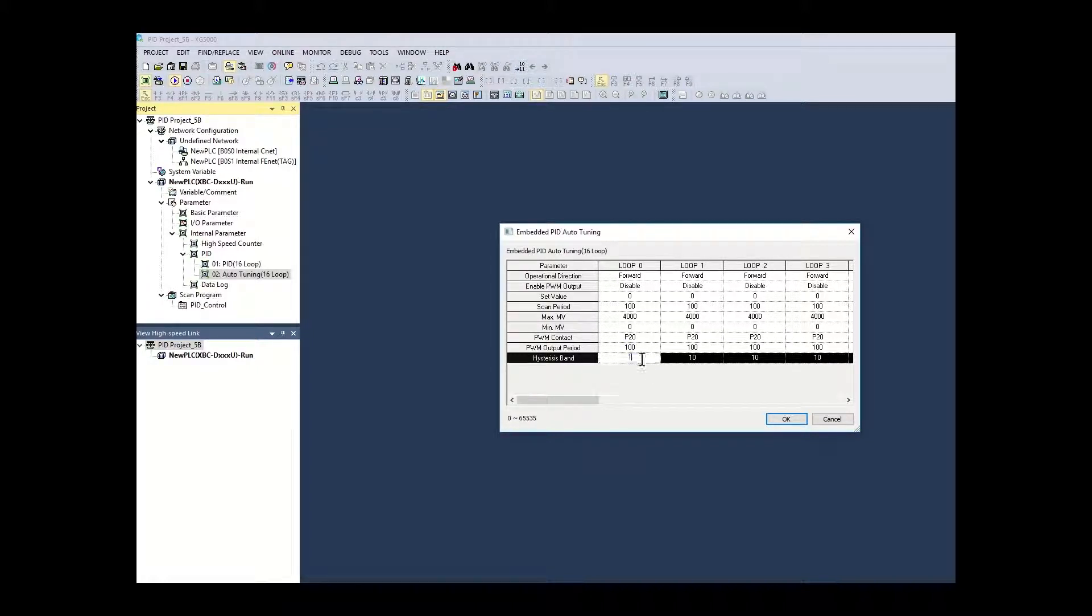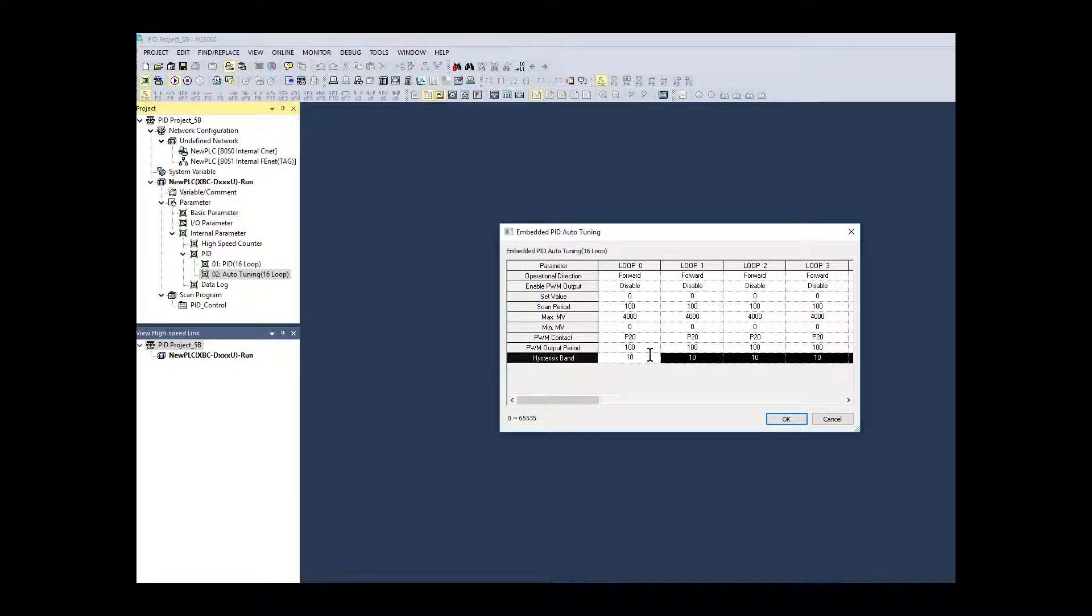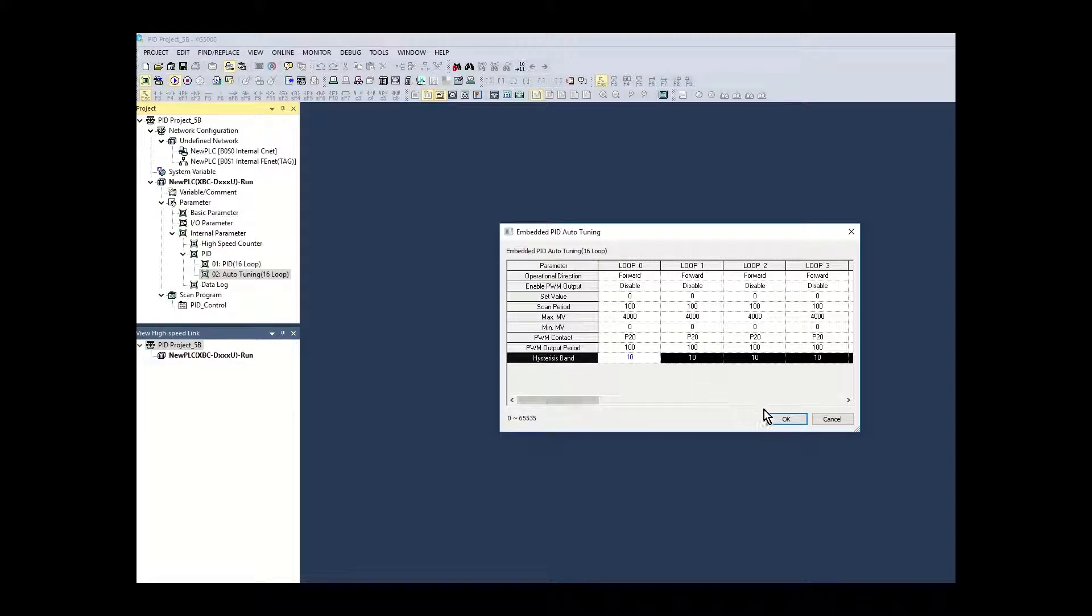For this application we will set the hysteresis to a value of 10. This will account for any signal noise of the PV around the SV. Click OK.